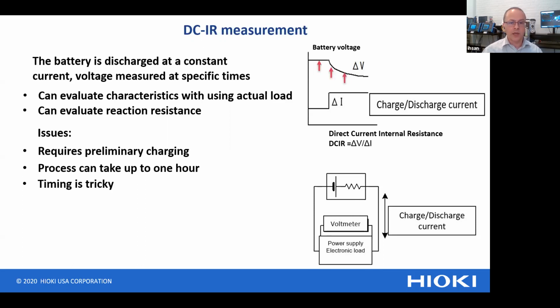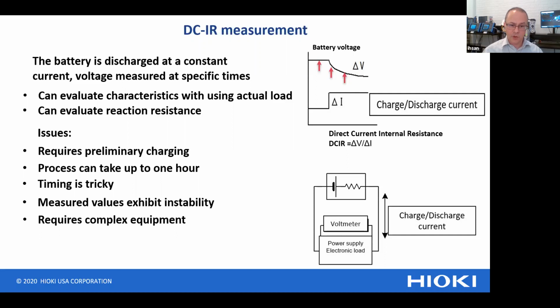And timing is also tricky because the way the DC resistance is defined is the change in voltage over the change in current. And we can see from the diagram here, the change in current is simply a step function. However, the change in voltage is time dependent. So your delta V is going to depend on when exactly you take the measurements. So that's why the timing is tricky with this method. And as a result, the measured values can exhibit a lot of instability. And also there's the requirement for complex equipment, and up to 100 amps or more may be needed when testing large batteries.